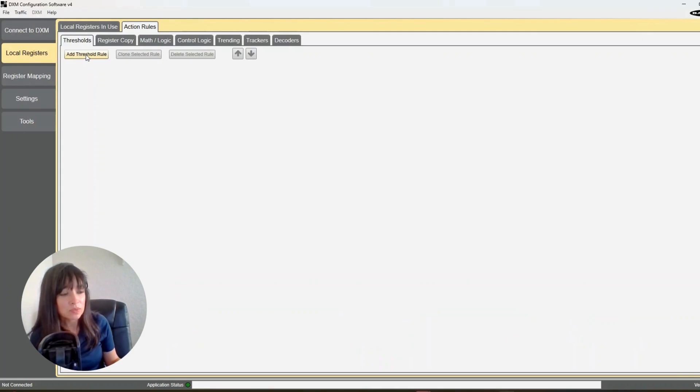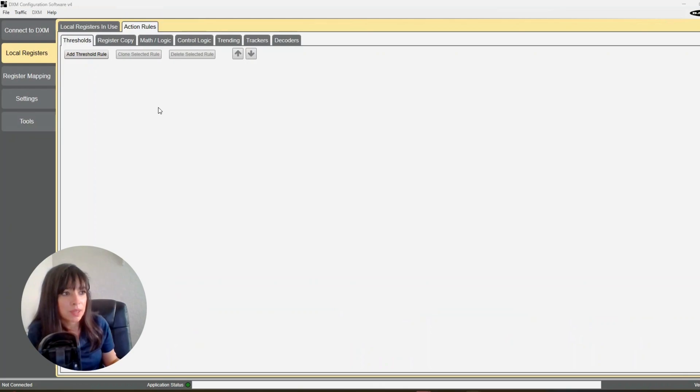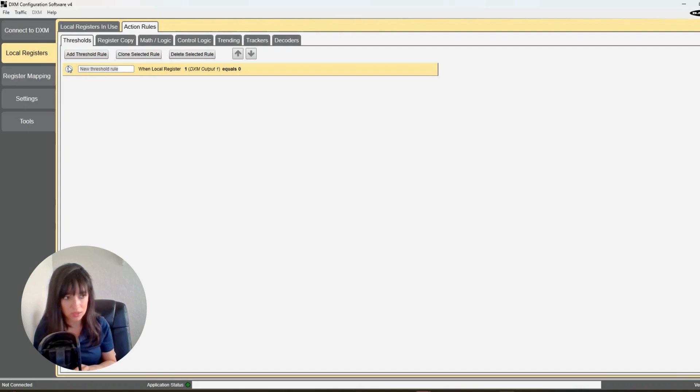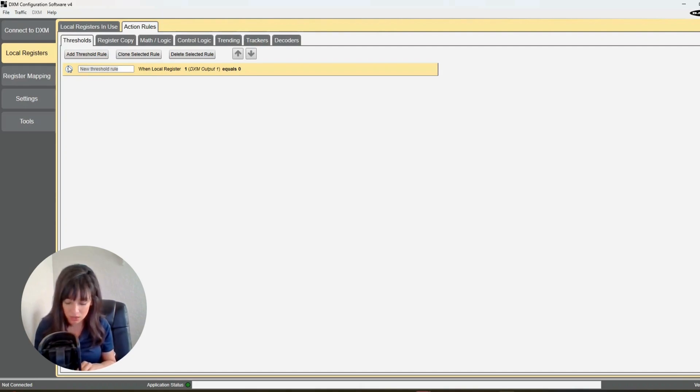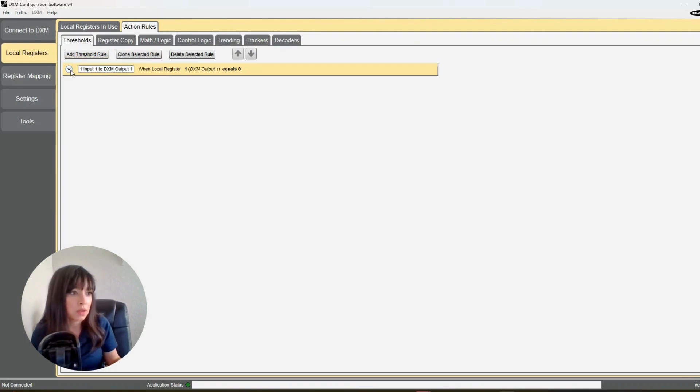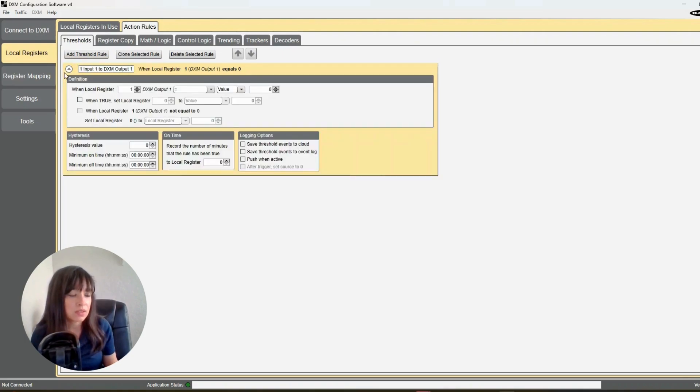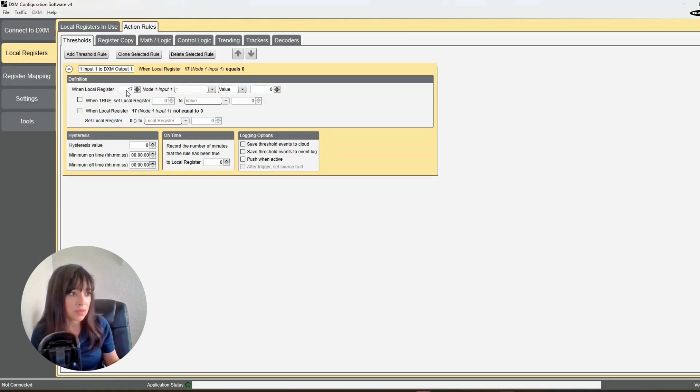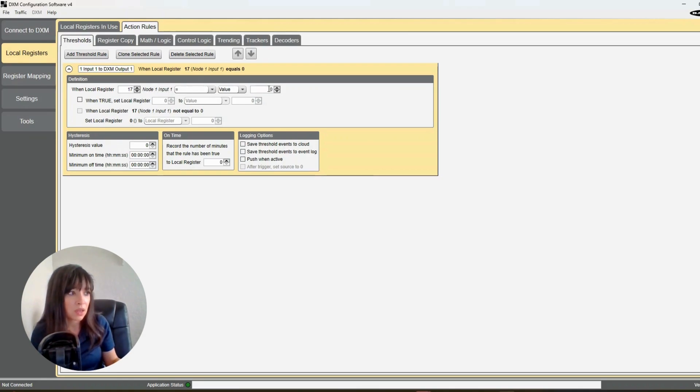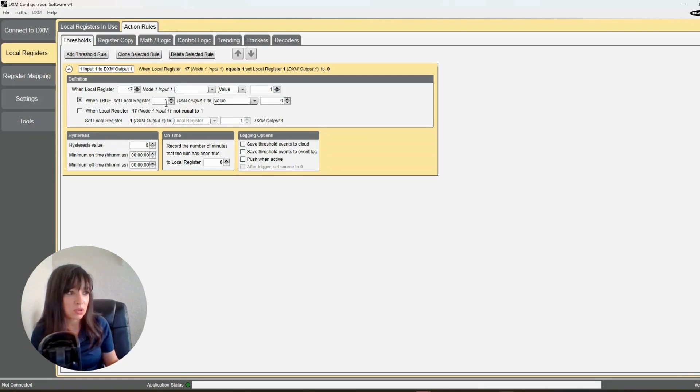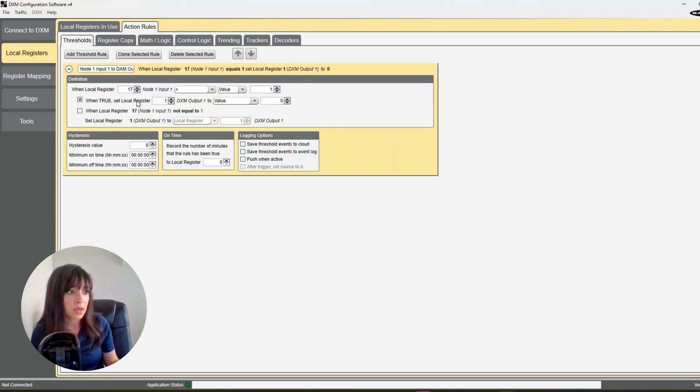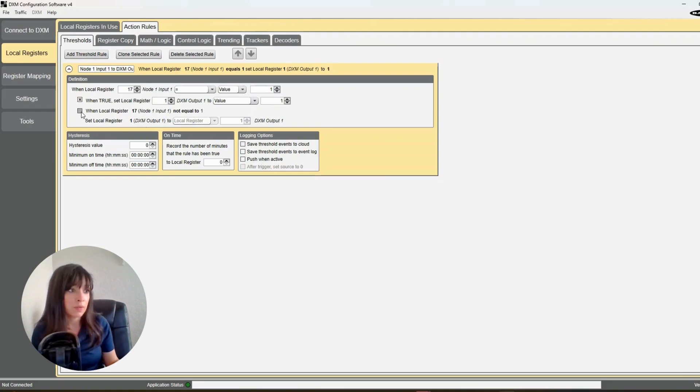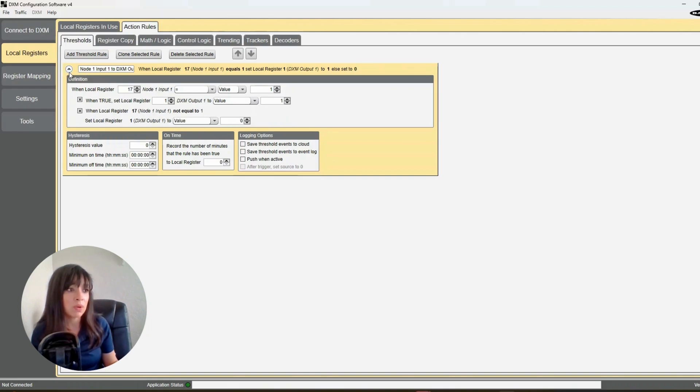So let's start with a threshold rule. Okay, so this threshold rule is going to give me some logic. What we're going to do here is give this rule a name. We're going to say node 1 input 1 to DXM output 1. So that kind of tells us what we're doing. We're just going to tell it when local register input 1 is 17, right? And this is nice, it auto-populates here. When that is equal to 1, checkbox, when this is true, I want to turn on 1, which is DXM output 1, to value of 1. And then when this is not equal to 1, then set it to 0, okay? So that's what we want for node 1 input 1.